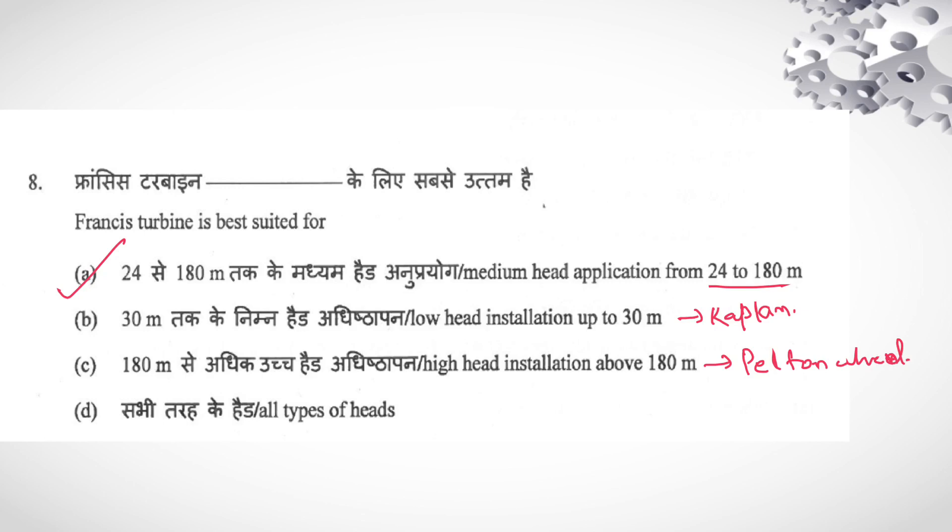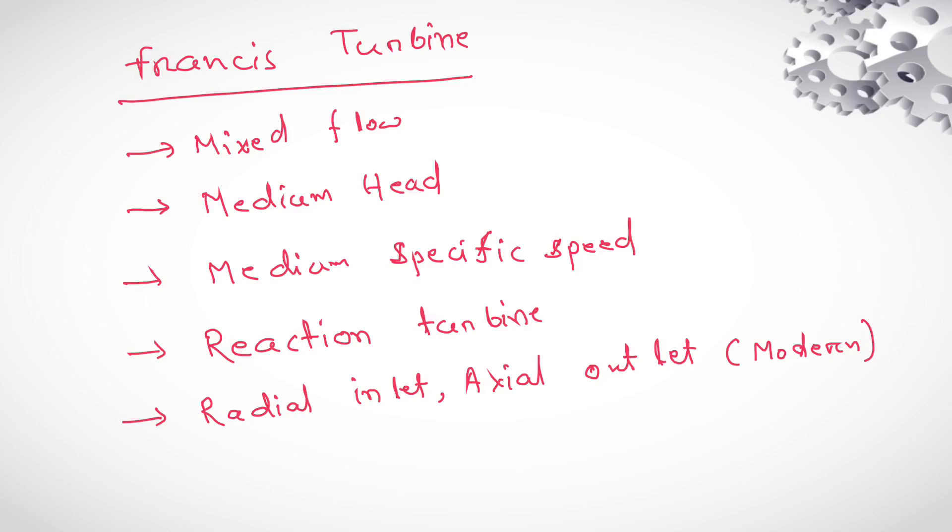Then for high head, they are using your Pelton wheel, Pelton wheel or your impulse turbine. And Francis turbine, it is a mixed flow turbine, it is used for medium head application, for specific speed also medium, it is a reaction turbine. And for modern Francis turbine, its inlet is radial and axial, outlet is axial, opposite of your centrifugal pump. In case of centrifugal pump, your inlet is axial and outlet is radial.